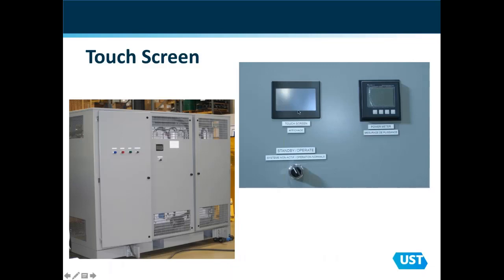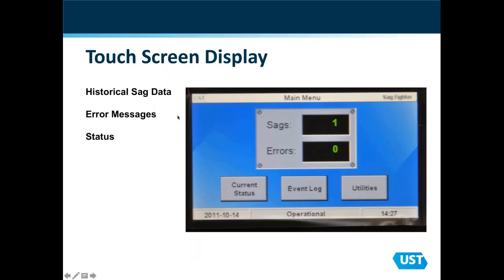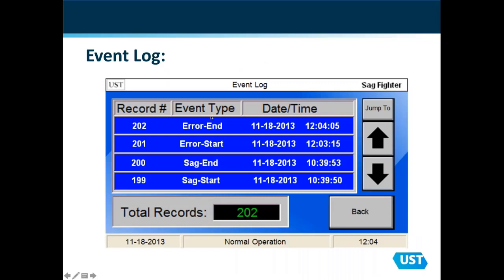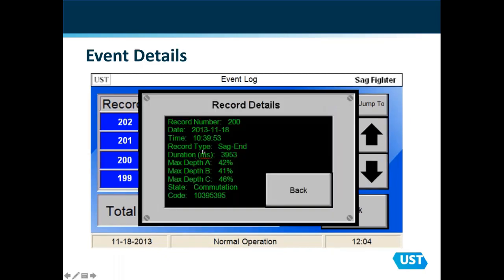The unit does come with a touch screen to interface with the unit. On the touch screen, you can capture historical data and any error messages, and it'll give you the status of the unit. So if you engage with the touch screen and look up your SAG history, the unit will give you a starting point and ending point, if you will, of any given SAG. And if you click on the SAG, it'll give you specific information about that SAG: what the voltage was doing across all 3 phases and how long that SAG event occurred, what the duration was. This is all accessed through the touch screen.